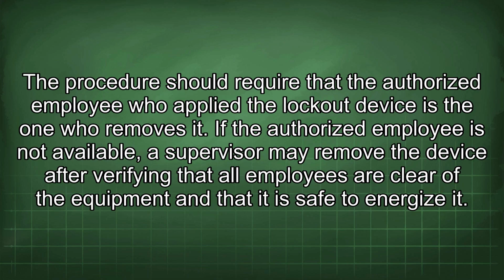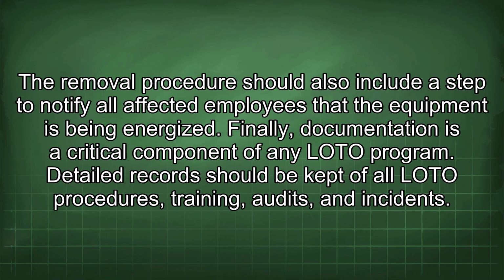The procedure should require that the authorized employee who applied the lockout device is the one who removes it. If that employee is not available, a supervisor may remove the device after verifying that all employees are clear of the equipment and that it is safe to energize it. The removal procedure should also include a step to notify all affected employees that the equipment is being energized.